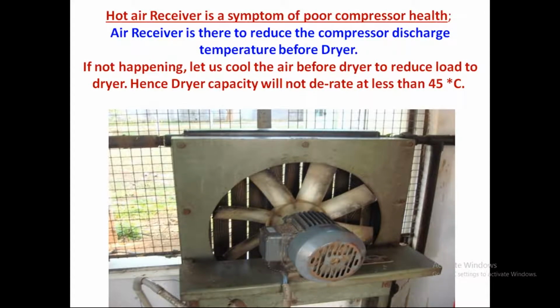In many of the industries, a decade back, they were using a post-air cooler. In fact, it is a good idea. Instead of having an integrated post-air cooler within the compressor hood, try to have the post-air cooler separately. If you want to maintain a deliverable temperature of 40 degrees, not 45 degrees, a separate post-air cooler will do a better job, and it will reduce the load for the refrigerant dryer also. Instead of buying one more refrigerant dryer, you just go for a post-air cooler that will maintain the same dryer, and it will maintain the efficiency and the performance excellently.